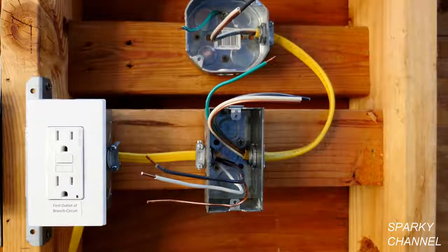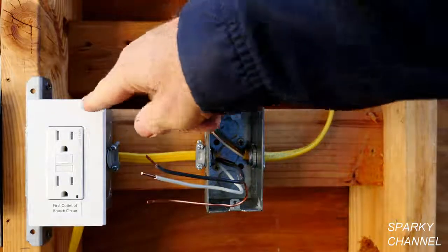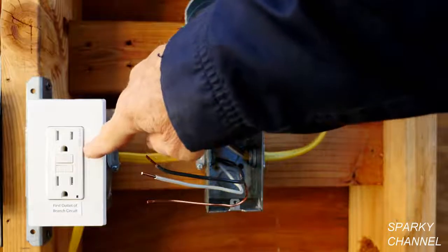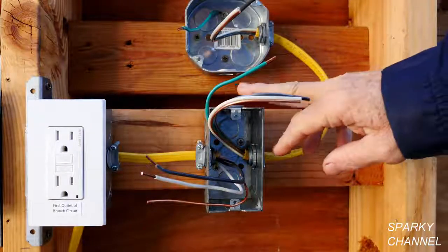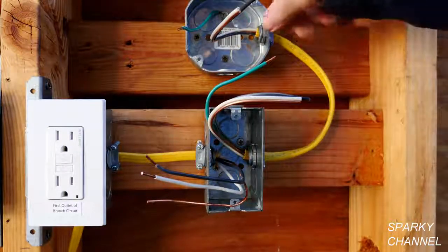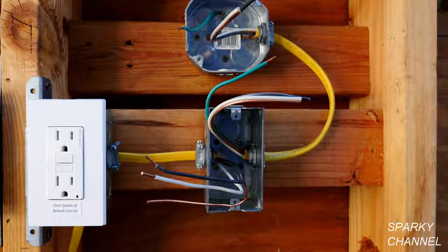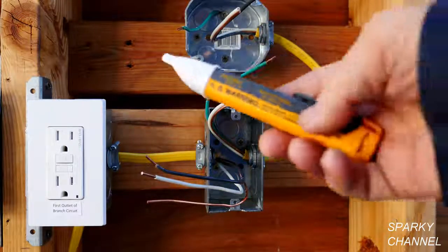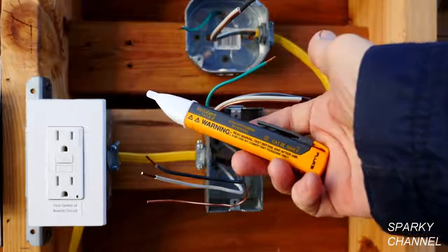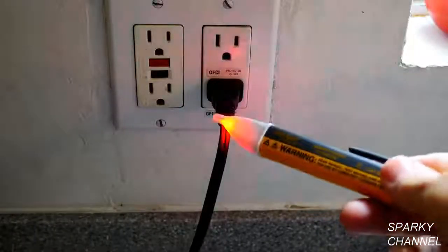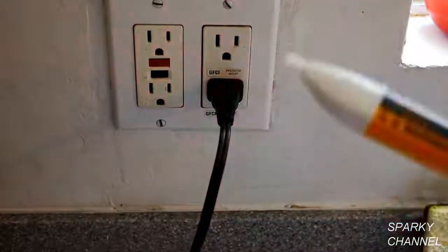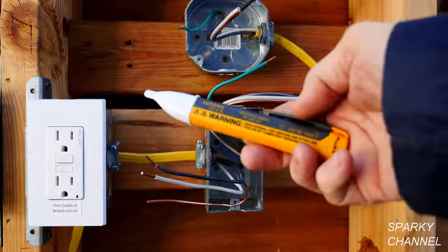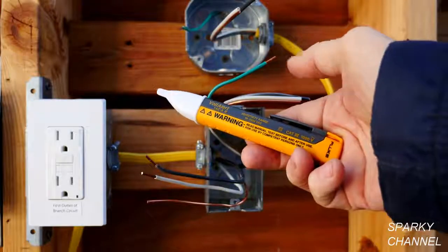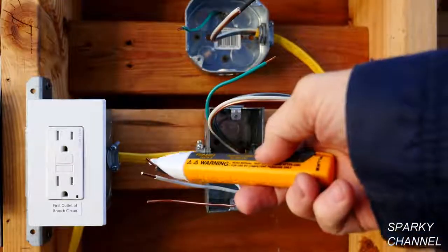So this circuit consists of a receptacle that does provide the AFCI and GFCI protection, and then we're going to have a combination switch and receptacle, and then we're going to have a light. The circuit breaker is off, but the first thing we need to do is test our voltage detector to make sure it works properly. I'll test the voltage detector on a known live circuit, and you can see that this one is working properly. Once we have tested our voltage detector, then we're going to ensure that the electricity is off.